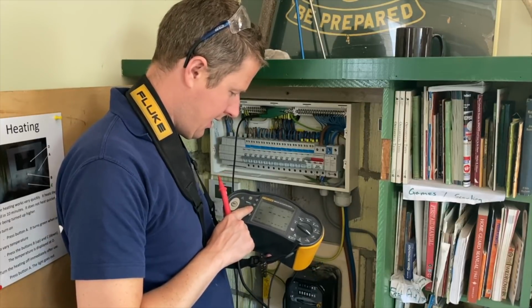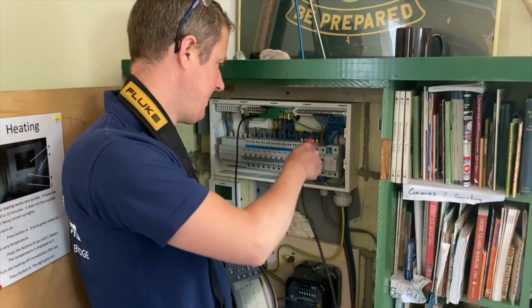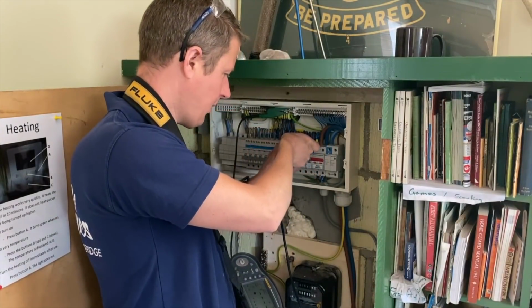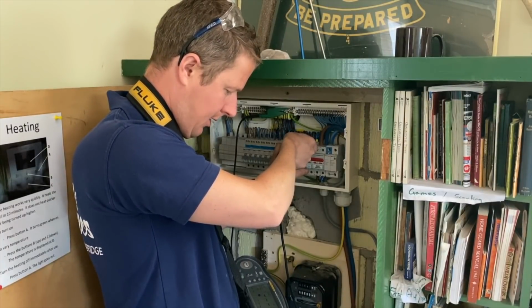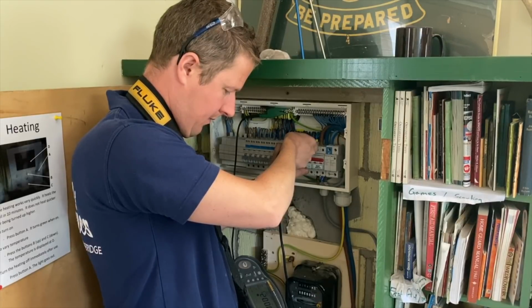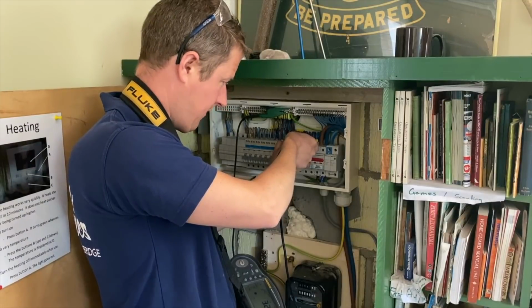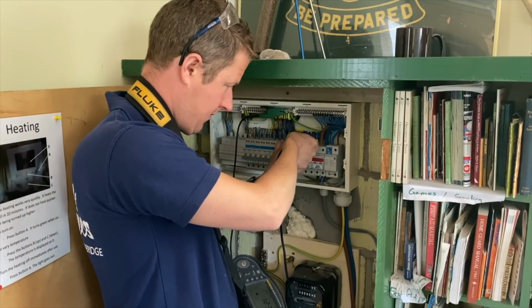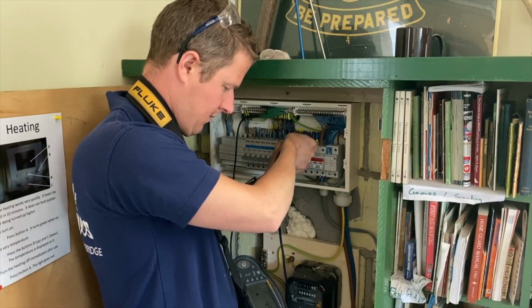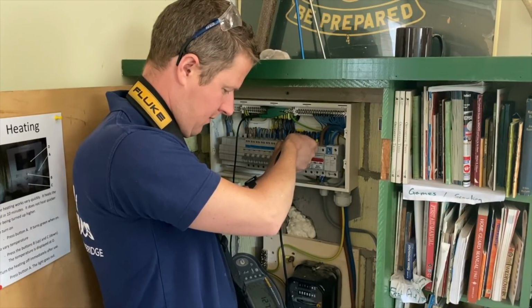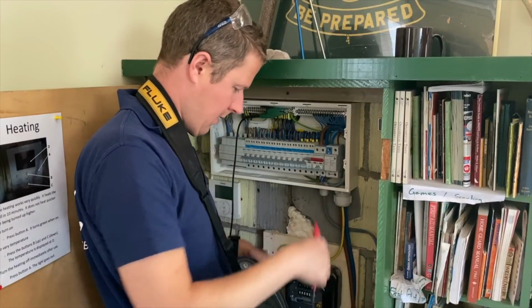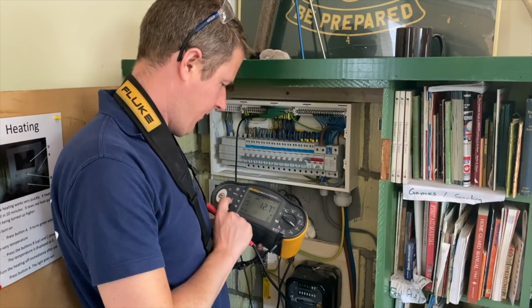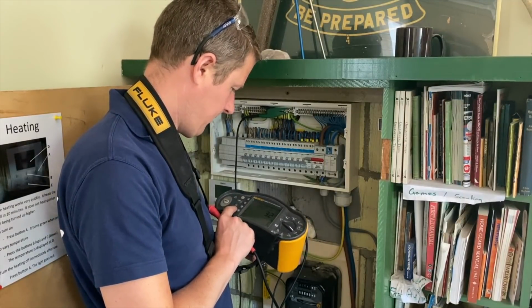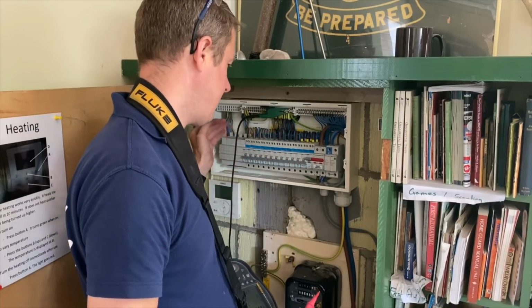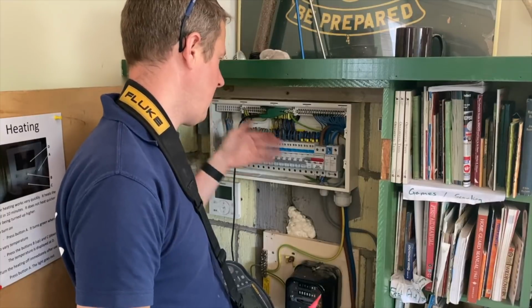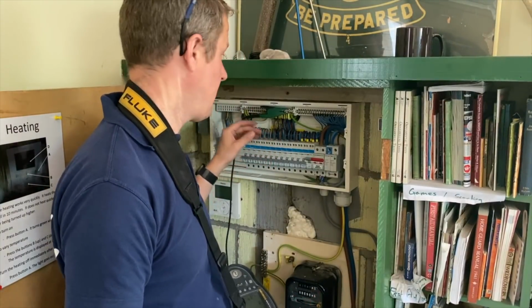Then we need to switch the tester to the DC setting for the pulsating DC, and then we do the same. So we run through another 6 tests, and again at half times it shouldn't trip. At 1 times it should trip, and it does. And there we go. So we've got the highest readings there. 5 times was 12.7 and 1 times was 12.3. So that's fine. And then we just do the same for all of these circuits. So just run through that for the whole lot. It's a little bit tedious, but it gets it done, and we write down the highest readings each time.